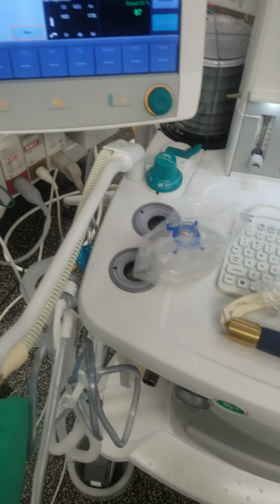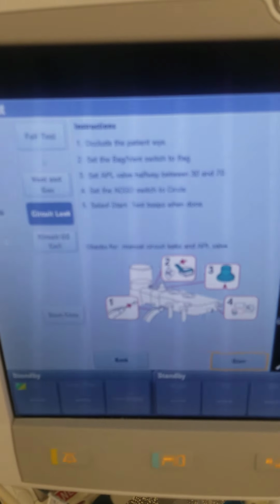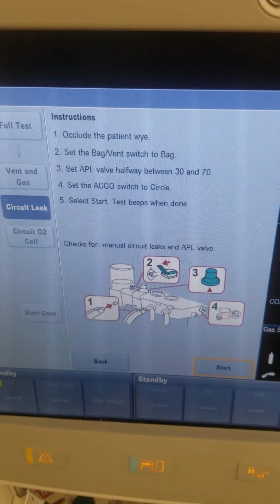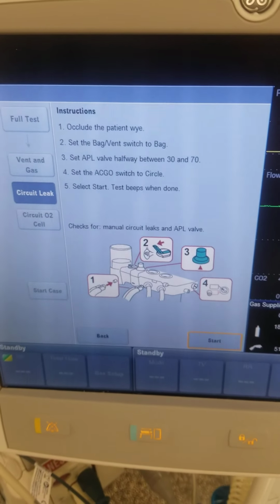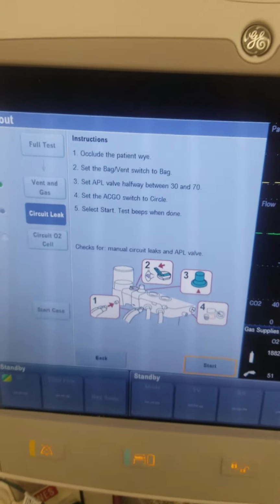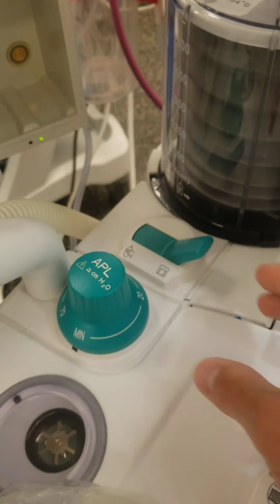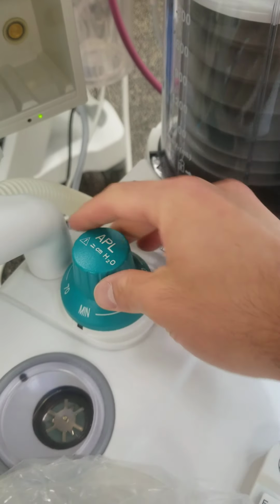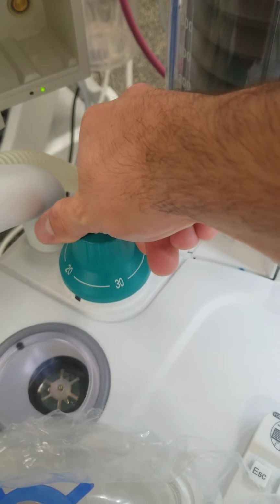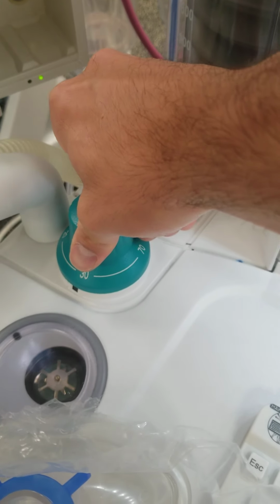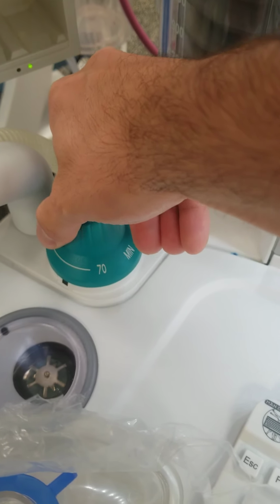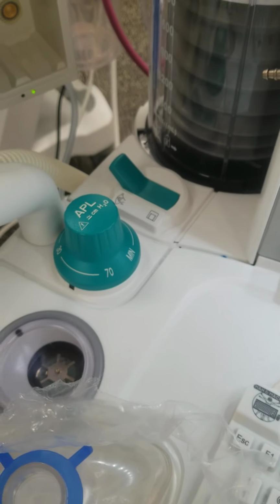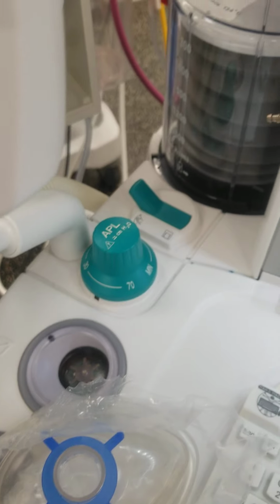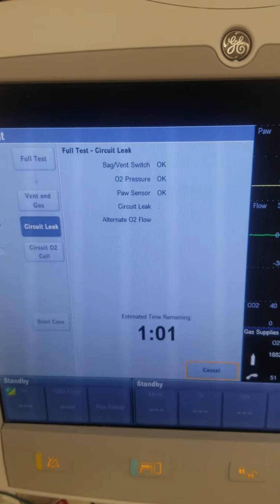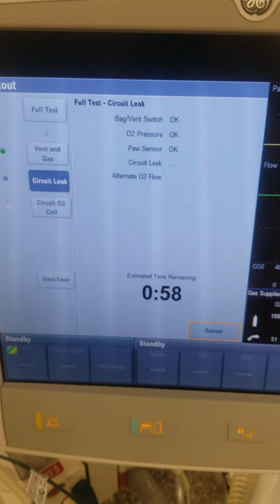All right, so again, it now alarmed again. So here's your next step. If you guys read that quickly, now it wants you to switch the setting to the bag mode, and then it wants you to keep it occluded, and you want to turn your pop-off to between 30 and 70. So I switch over. When I close my pop-off, imagine putting more of your thumb over the hose, so air can't come out, and it causes a back pressure in the bag here. So I hit start, because that's occluded between 30 and 70. It's not too picky. It's going to go through that check, and now it's actually checking that circuit for compliance and also for leaks.